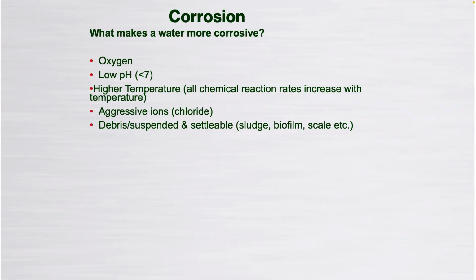And then debris in suspended or settleable solids. So that's your sludge. It could be biofilm where you've had bacteria, and it could be scale. Those things essentially are very corrosive to the system. And then velocity makes water more corrosive. So as I mentioned earlier, if it's low, we're inviting things to settle out. And if it's high, we can start to cause erosion around the system.